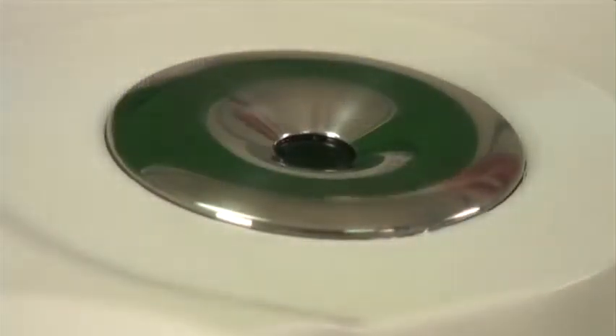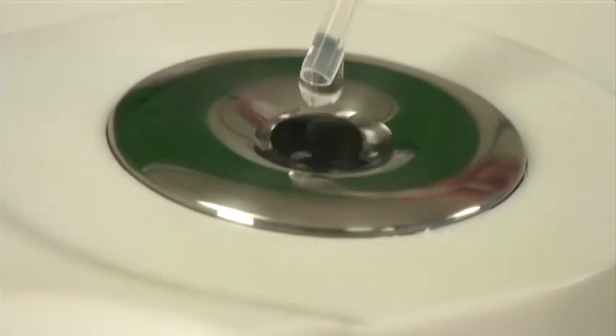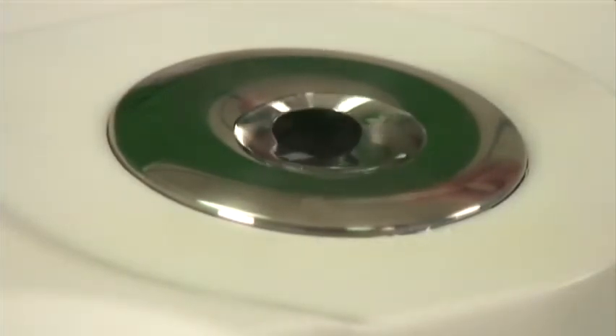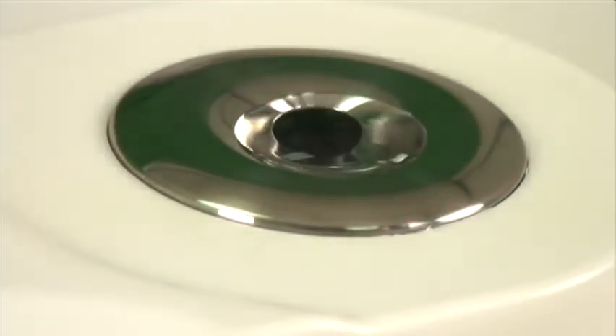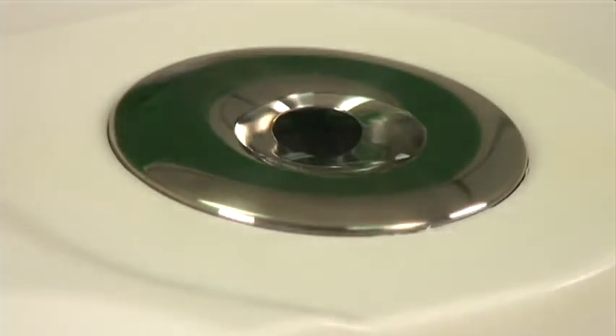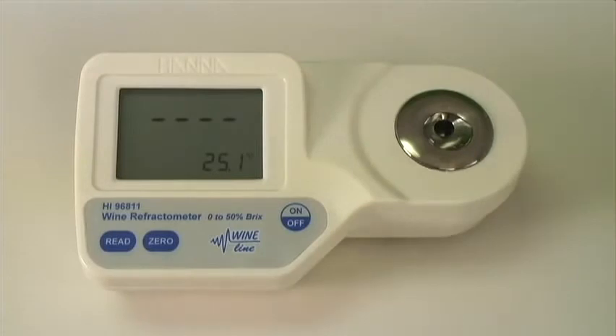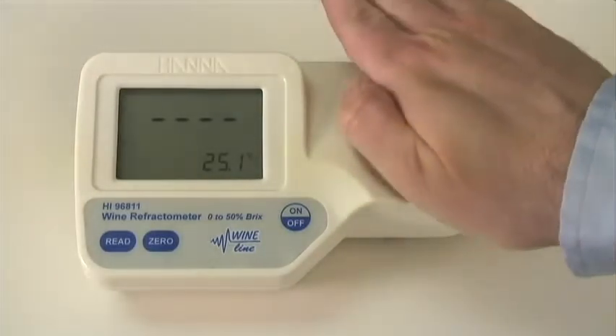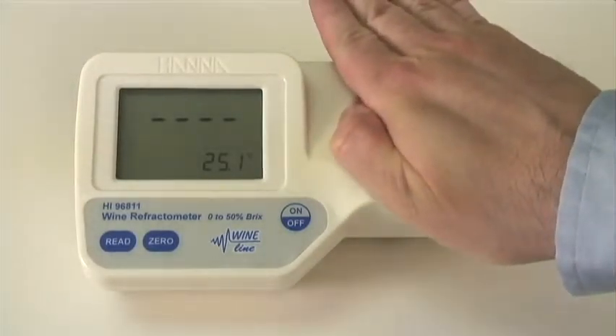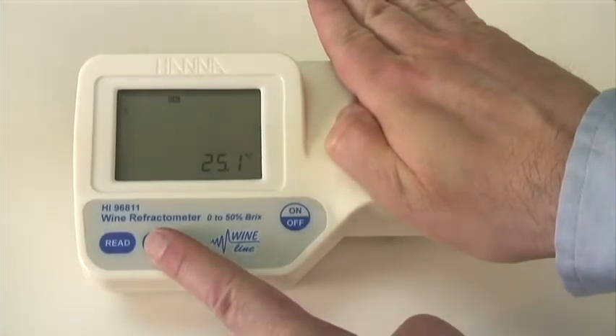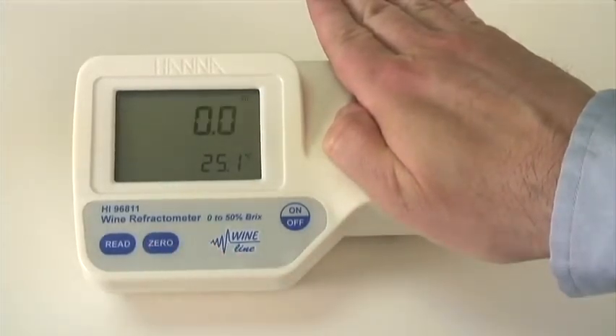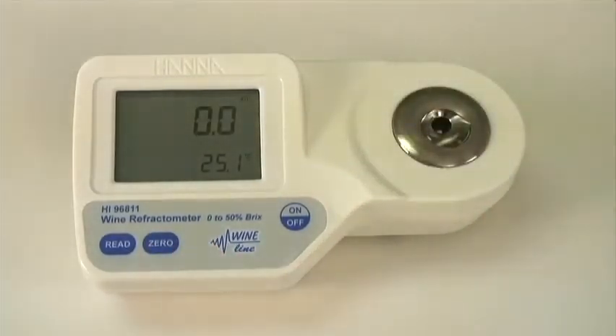First, fill the sample well with deionized water. I'm using a plastic pipette. You don't want to use anything metal like a spoon that could scratch the prism. Make sure the sample completely covers the prism and that there are no bubbles on the prism. If the sample is subject to intense light, you may want to cover the sample with your hand or other shade. Second, press the 0 key. If no error message appears, your unit is calibrated.